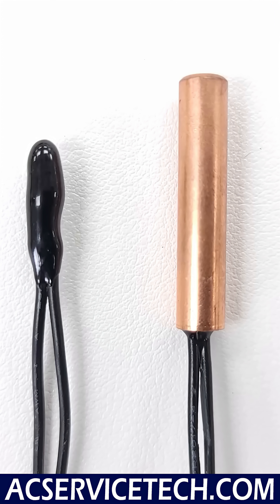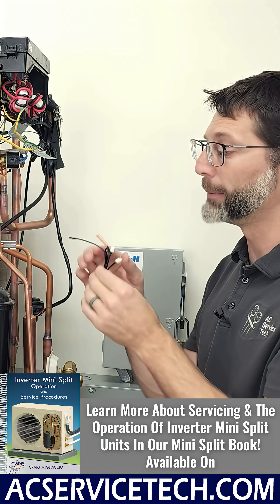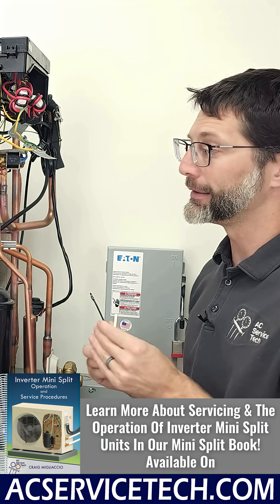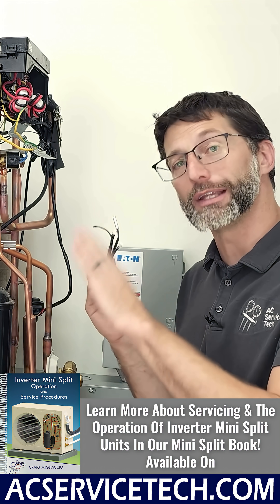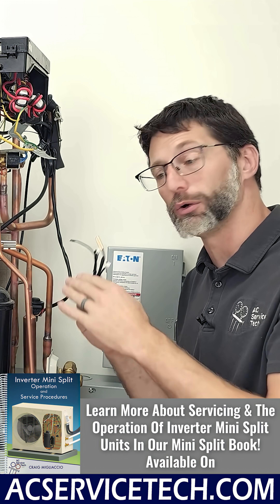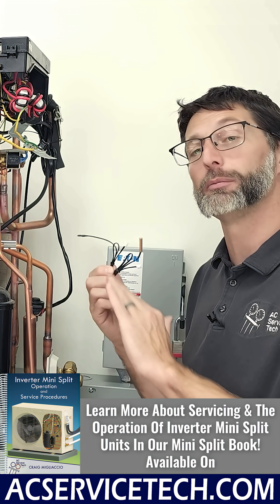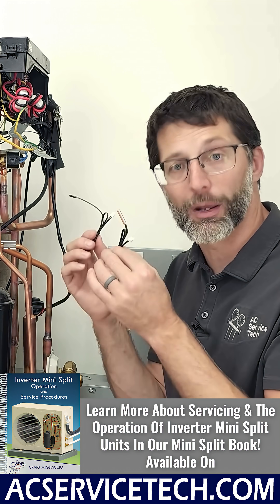There are two types — bead and tube — and you'll want to troubleshoot them with the power off. The indoor unit may also throw an error code identifying the problem, which is a helpful diagnostic feature of mini-split systems.